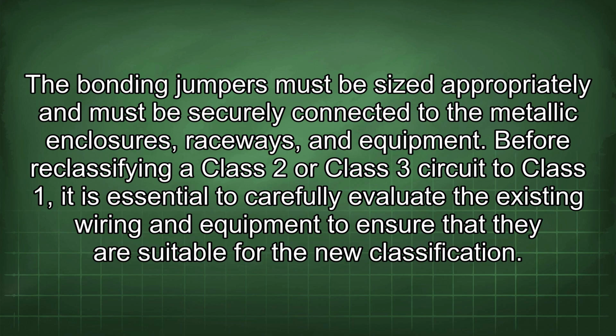Before reclassifying a Class 2 or Class 3 circuit to Class 1, it is essential to carefully evaluate the existing wiring and equipment to ensure that they are suitable for the new classification.